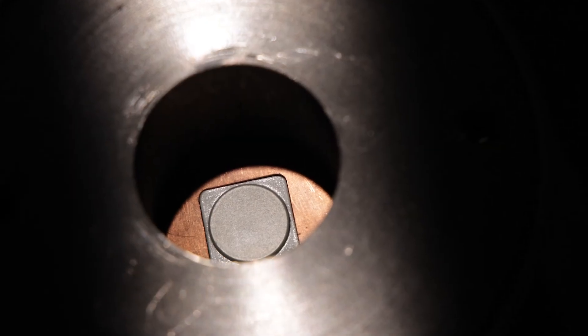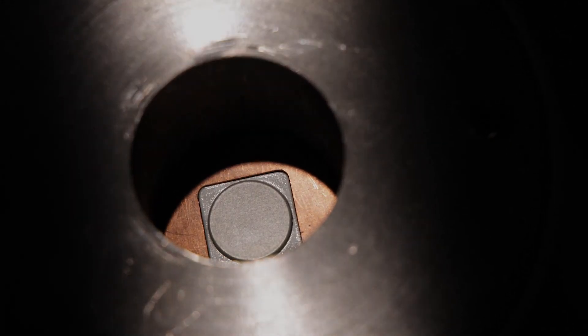The CZT's space-saving design doesn't compromise on performance. The new CZT detectors are highly sensitive across an energy range of 20 keV to 3 MeV, making it an ideal solution for identification of impurities in a sample at a higher resolution.